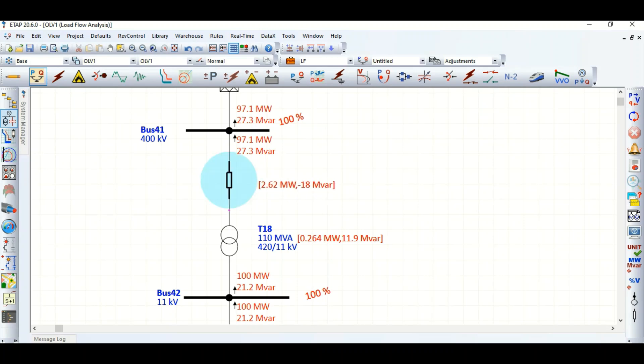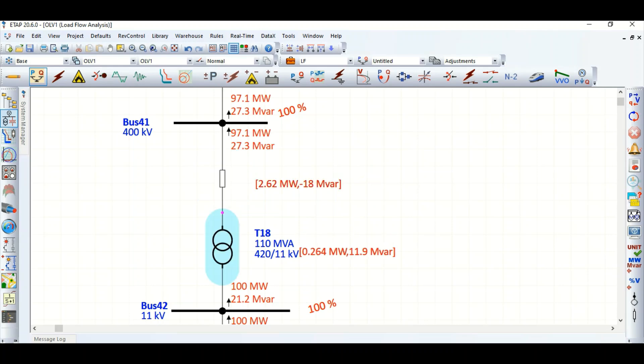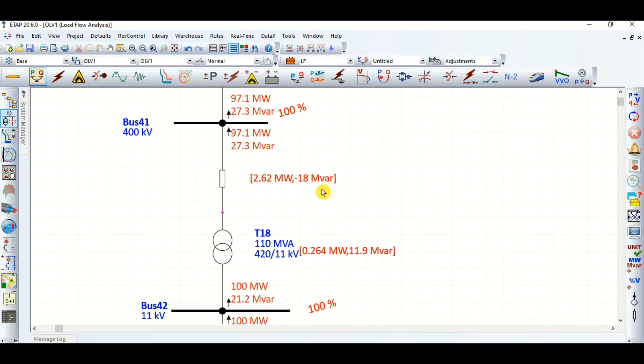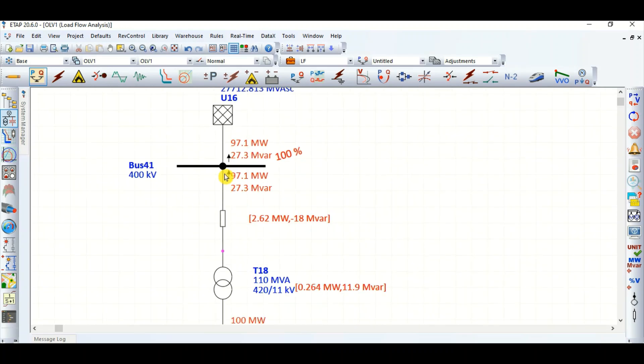There is also minus 18 MVAR from the transmission line, meaning the transmission line is contributing 18 MVAR towards the generator bus — that's why it is negative. So the net MVAR supplied towards the grid is 27.3 MVAR.